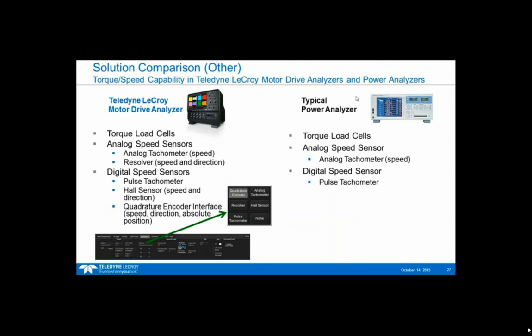When you look at torque and speed sensing, the motor drive analyzer has a little more capability. It can handle a resolver from the analog speed side for speed and direction, and on the digital speed side, it can also integrate hall sensor information for speed and direction, and a quadrature encoder interface for speed, direction, and absolute position, whereas the typical power analyzers have very rudimentary torque and analog tachometer and perhaps digital pulse tachometer integration. Again, this really stems from the fact that the power analyzer has historically been used as a validation tool on a test bench with a dynamometer, and these are the kinds of signals dynamometers have, whereas designs in the field typically use hall sensors, quadrature encoders, or resolvers.